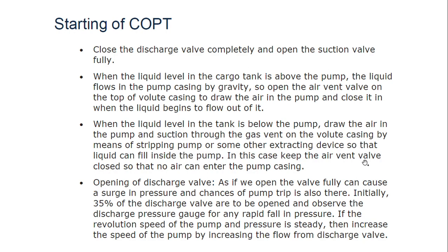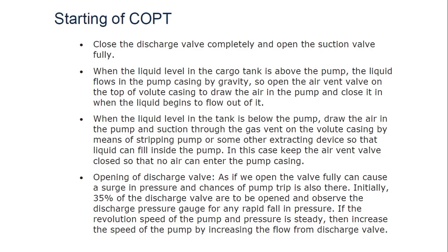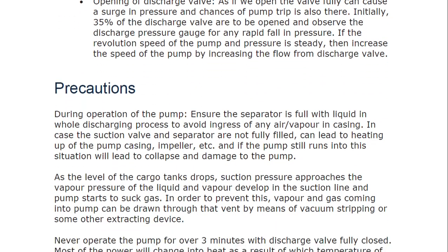When opening the discharge valve, opening it fully can cause a surge in pressure and there are chances of pump trips. Initially, 35 percent of the discharge valve should be opened and the discharge pressure observed. Once the pressure is steady, then we open it fully.